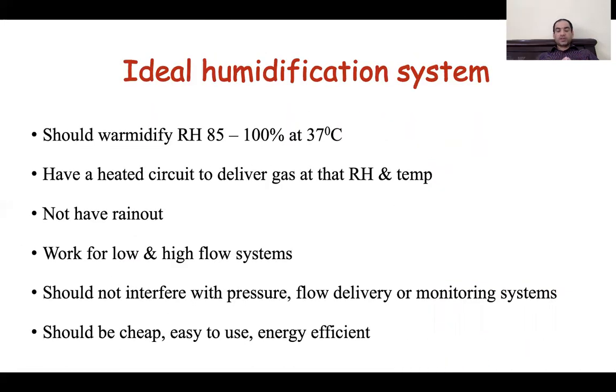What is an ideal humidification system? An ideal humidification system is one which is able to warm and humidify gases at 37 degrees Celsius with a relative humidity of 85 to 100%. It should have a heated circuit to deliver gas at the set relative humidity and temperature. Ideally, it should be servo-controlled, with no rain-out in the inspiratory limb. It should work for both low and high-flow devices, should not interfere with pressure, flow delivery, or monitoring systems, and should be cheap, easy to use, and energy efficient.